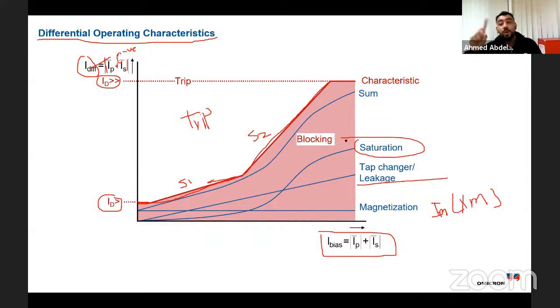So I will expect the worst case scenario of a saturation of any of these CTs, and I will see the maximum slope or the maximum error that can happen. Then I will plot all of them together. Then I need to sum all errors to find exactly what is the maximum error that can happen in case of normal operation. So I will draw the characteristic here, the summation, which is the summation of error number 1, the magnetization, error number 2, tap changer and leakage, error number 3, the saturation. So at the end, I will have the summation of all of them.